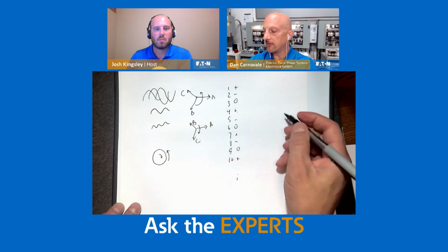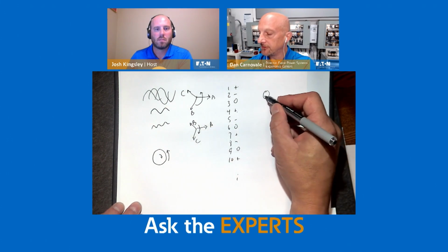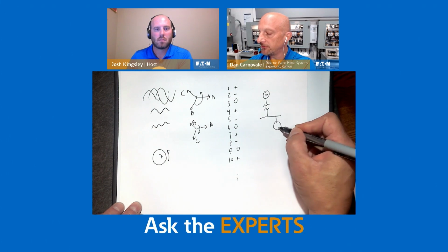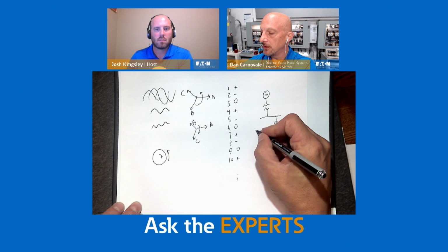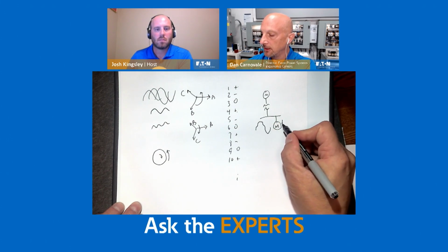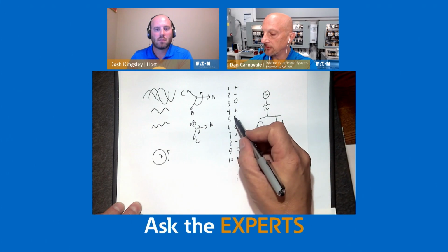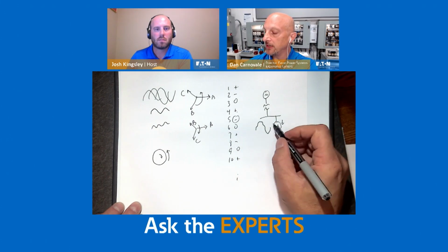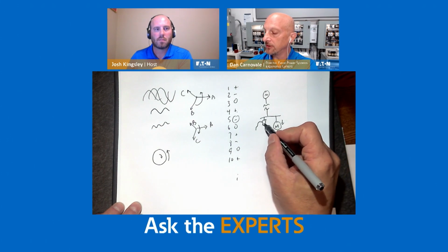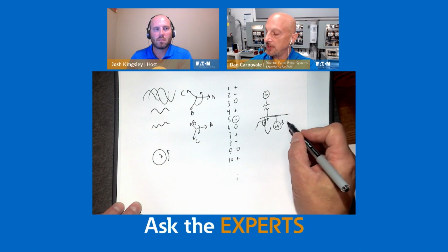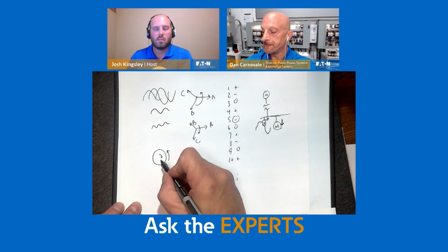So when you have a system with enough voltage distortion on my bus here, even an across the line motor might see a voltage that looks like that, which means it's going to draw a current that might be, for example, a negative sequence harmonic, like the fifth harmonic. So maybe with some VFDs over here, I'm creating harmonic currents that go out, and I'm screwing up my bus voltage. And then that negative sequence harmonic current comes into this motor, makes it want to spin backwards.